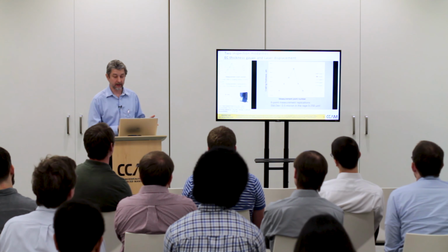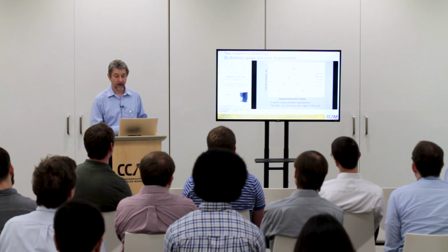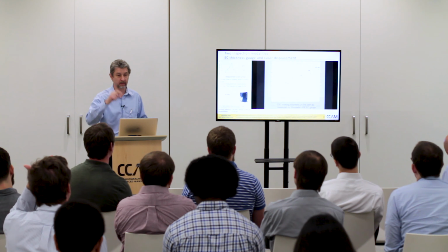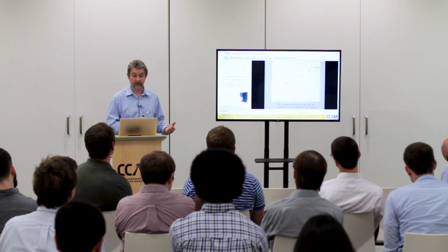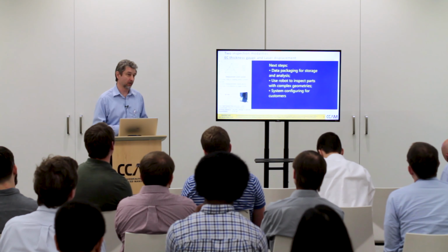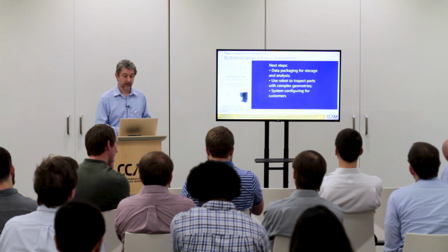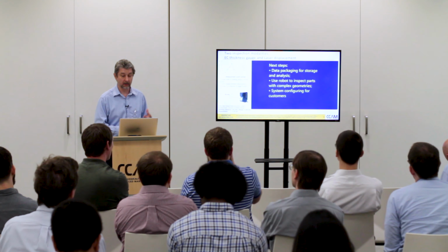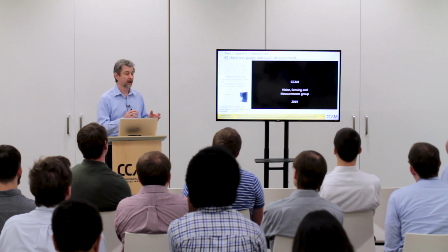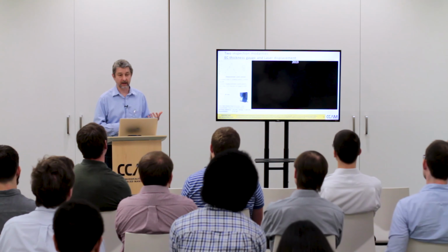That result is five replications of the same scan, with very high precision down to 0.5 microns, and this is the actual result that we got from the TBC measurement. So again, the system shows the concept of multiple sensor combination and a way to automate and make non-destructive testing or metrology measurement more reliable and more reproducible.